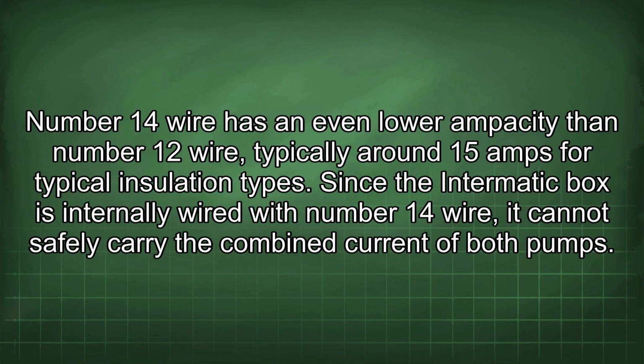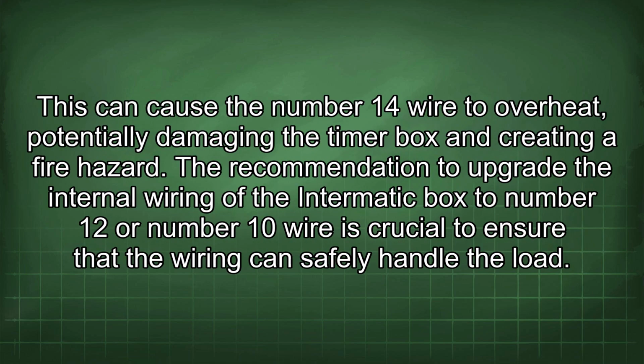concern. Number 14 wire has an even lower ampacity than number 12 wire, typically around 15 amps for typical insulation types. Since the Intermatic box is internally wired with number 14 wire, it cannot safely carry the combined current of both pumps. This can cause the number 14 wire to overheat, potentially damaging the timer box and creating a fire hazard. The recommendation to upgrade the internal wiring of the Intermatic box to number 12 or number 10 wire is crucial to ensure that the wiring can safely handle the load.